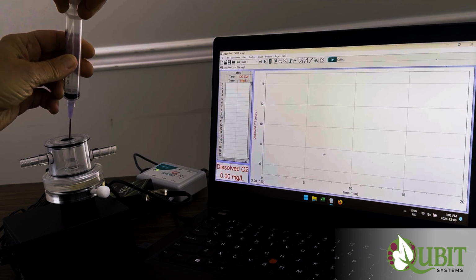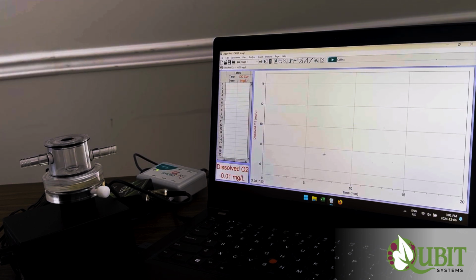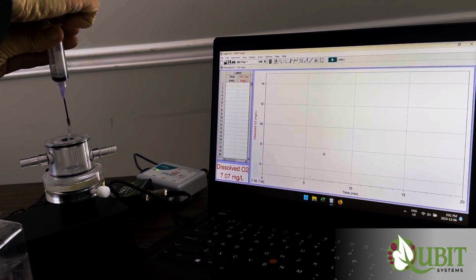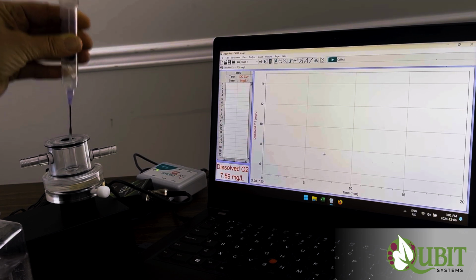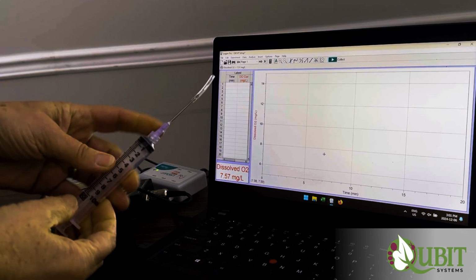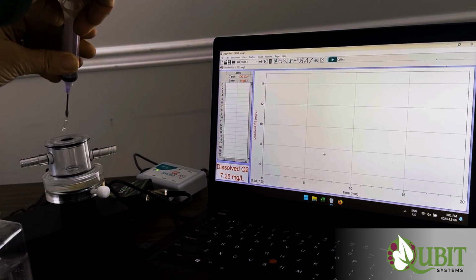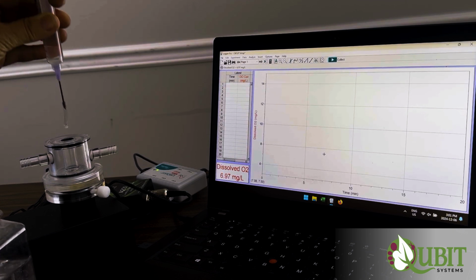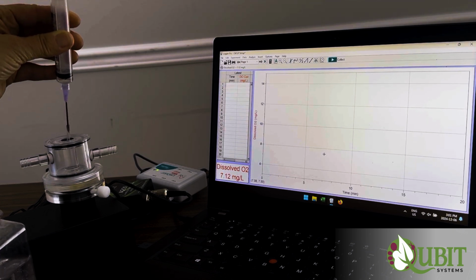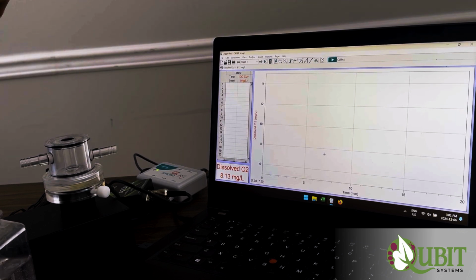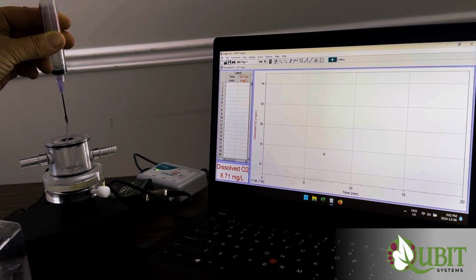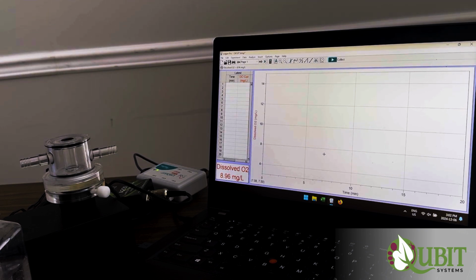Before proceeding with the experiment, it's super important to get rid of this solution, okay, and rinse your electrode really well with fresh water to get rid of any traces of sodium sulfite. That is why I'm using here a syringe with a soft tubing tip, so I can add water to rinse it and then suck it back out to remove it and dump it without puncturing or damaging the membrane which is at the base of this electrode. Okay, so I've done that a few times, but one can certainly continue to rinse.